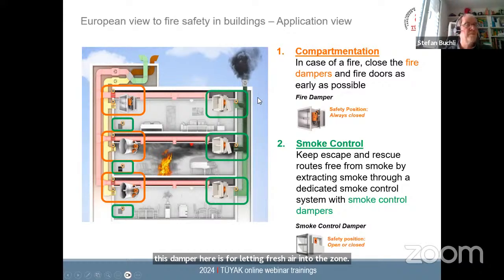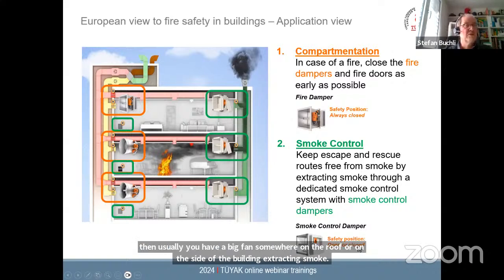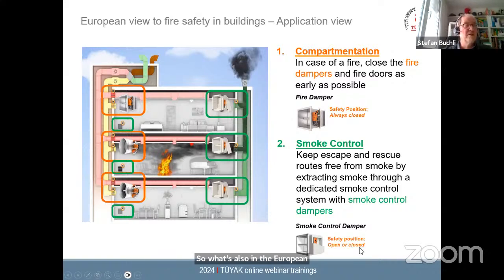extracting the smoke. What's also in the European standard is that for the application of smoke control dampers, only non-spring return actuators are allowed. So this is really defined by the standard. This is the big difference here.